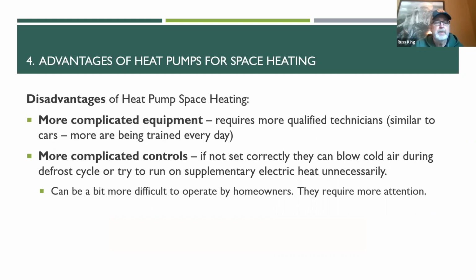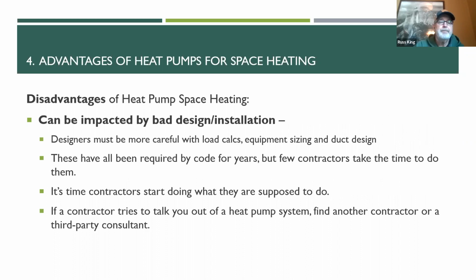So the disadvantages of heat pumps: the equipment is more complicated in terms of controls and motors and things like that. They're not safety devices, but they're things to make it more efficient. And so it does require a higher skilled technician to work on them. And the controls are a little more complicated too. They behave a little differently than a gas furnace. So you have to be more conscious about how they're operated and how they're controlled and how you operate the thermostat and things like that.